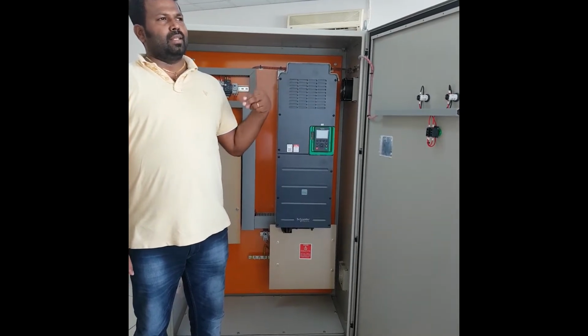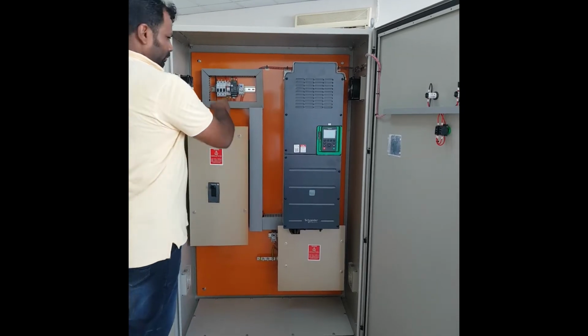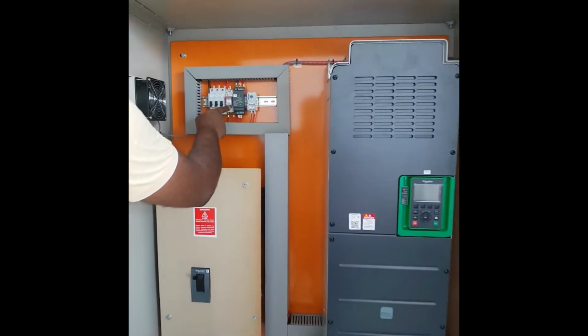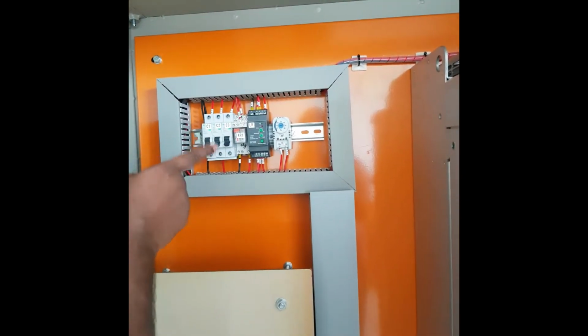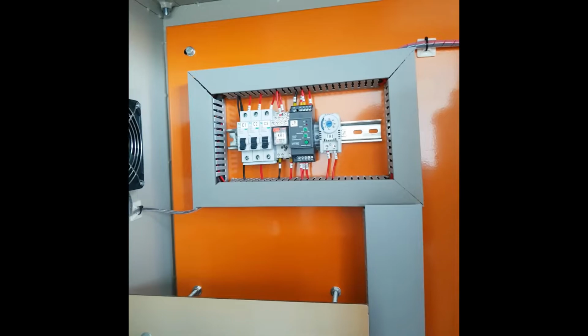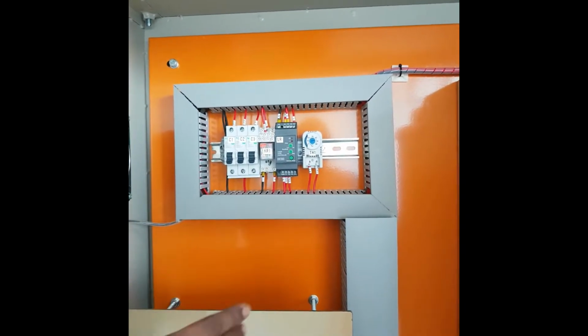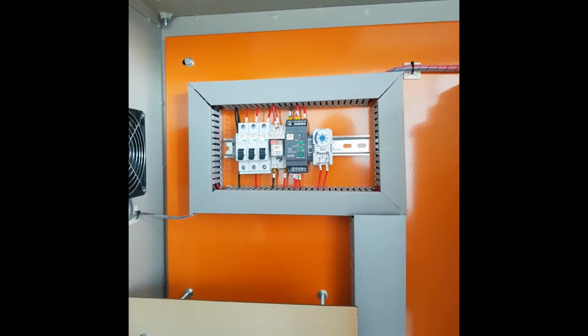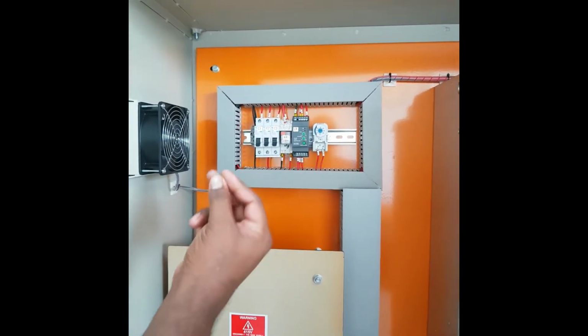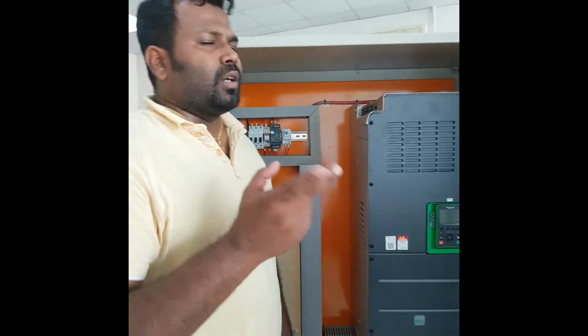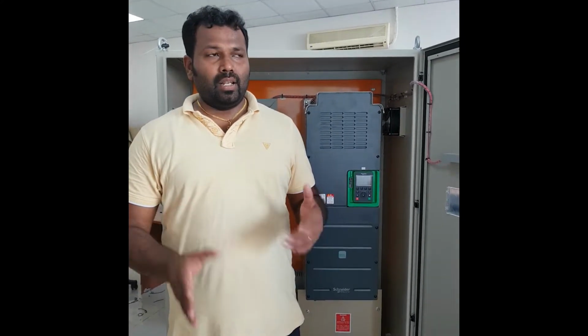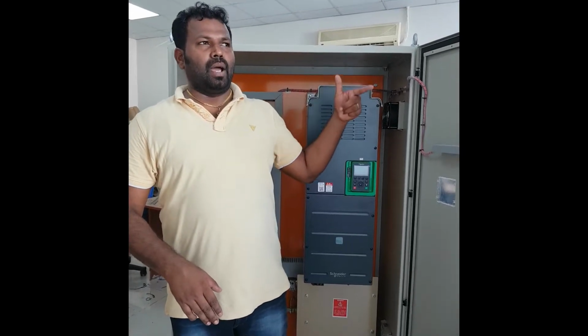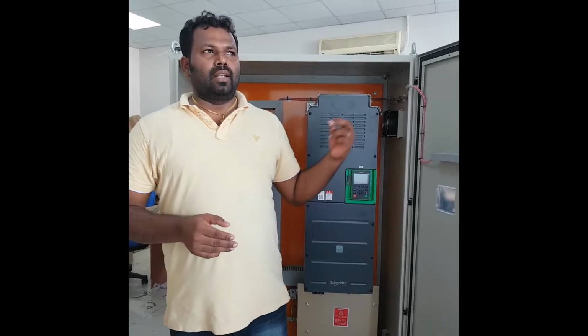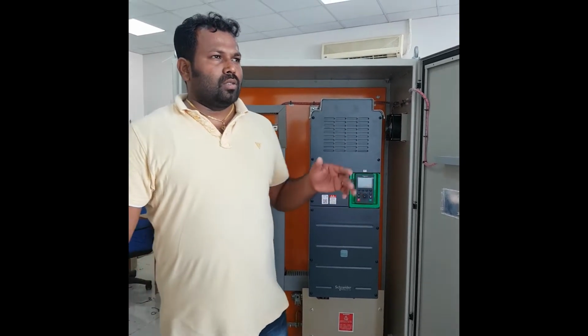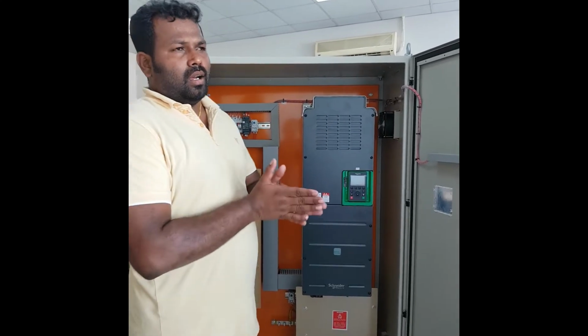In this case, we have provided dry run protection with a level relay. You can see the level relay we have provided. This level relay senses the water level in the borewell. It has a provision for connecting a probe electrode, called a level sensor, which is dropped to the water level. Once there is enough water, the level relay will sense it and allow the panel to run. When there is no water, the level relay will sense that and de-energize the circuit, so the pump does not run. This is the basic protection for all borewell operation.